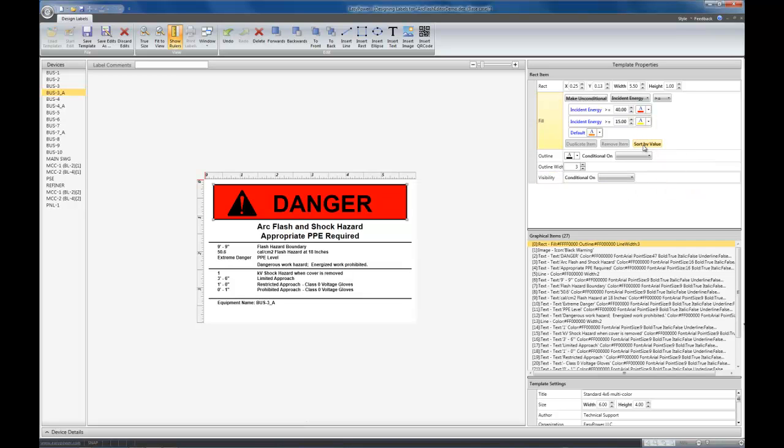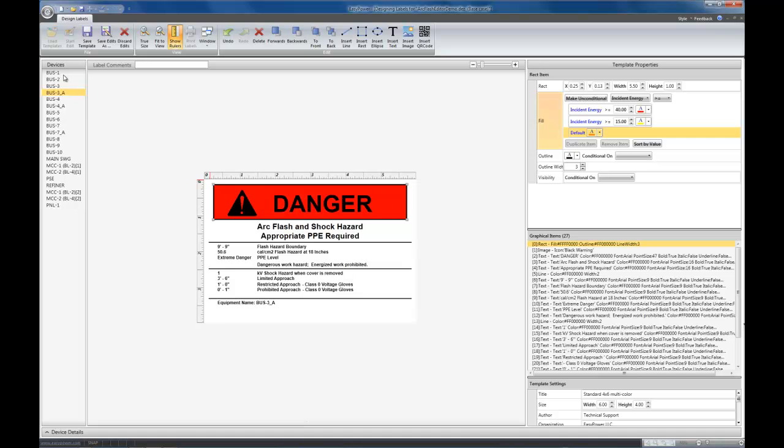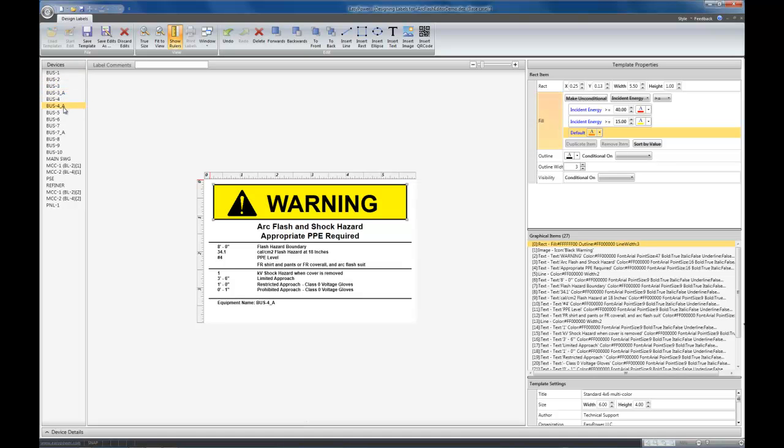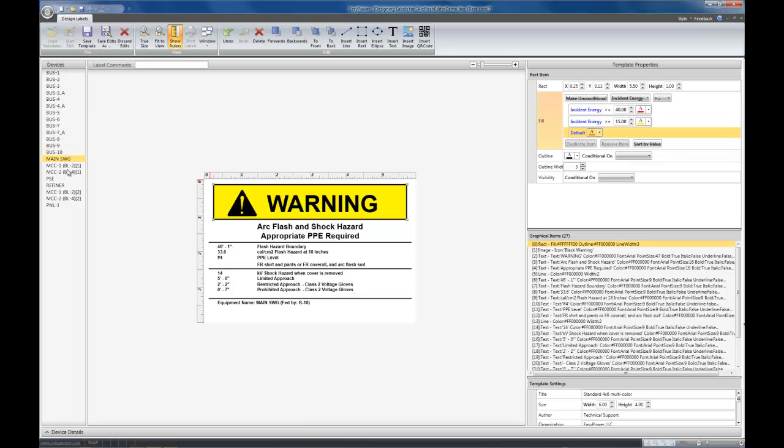Sort it so that it evaluates in order. Now, when the incident energy is greater than 40, it's going to be red. When it's greater than 15, it's going to be yellow. Otherwise, it's going to be orange. If you scroll through your devices now, you'll notice it changes from orange and yellow and red, based upon which device you have selected.